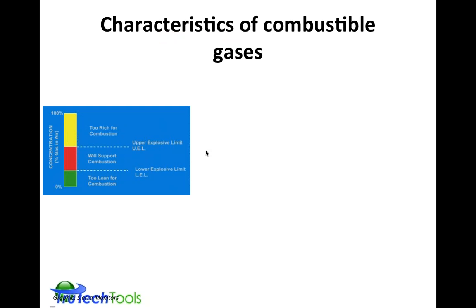So what's a characteristic of a combustible gas? You'll see in the chart over here, we talk about the concentration, the percent of the gas in air. In the green area, it's too lean for combustion. There's not enough gas for the amount of oxygen present for combustion to be ignited. In the red area, it will support that. And then you can actually get too much fuel to the air, and you'll get into the yellow area where ignition won't happen. The dangerous aspect here is when you rise above the upper explosive limit, if the air clears, it'll drop back down into the danger zone and support combustion.